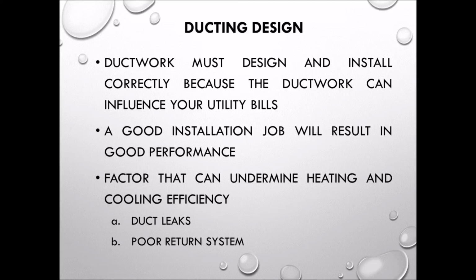So, for the ducting design for this office, ductwork must be designed and installed correctly because the ductwork can influence our utility bills. A good installation job will result in good performance. Factors that can undermine heating and cooling efficiency are duct leaks and a poor return system.